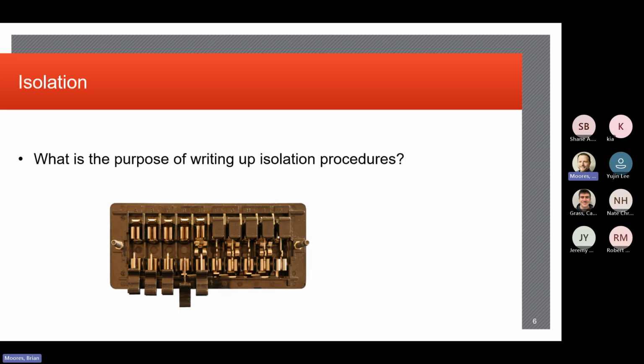Think about the one line that we had up on the screen, and we had a Bangor line and a Boston line, and we were trying to isolate the three relays that were associated with that one line. But we didn't want to affect any of the other power system, the other line or the transformer, right? So we write up these procedures, we establish the procedures, and we go through our due diligence to make sure that we are only isolating the things that we are working on, and we are fully isolated, and we don't have any impact on the things that need to remain in service. So we write up those procedures to make sure we don't disturb the things that need to remain, and we only truly isolate the things that are inside our zone of clearance or our work zone, because we do not want to have misoperations. We do not want to trip off things if they're in service. So we got to be mindful of that.